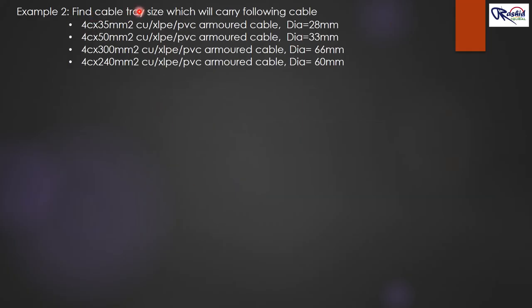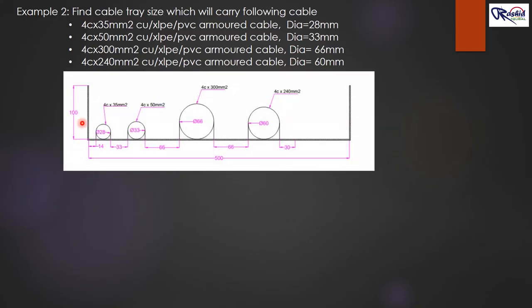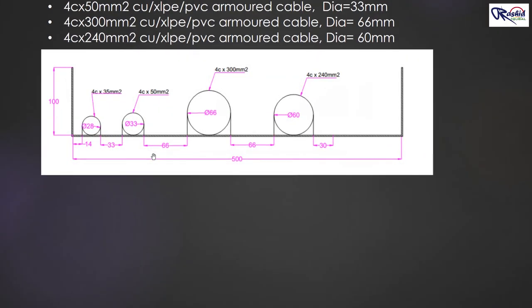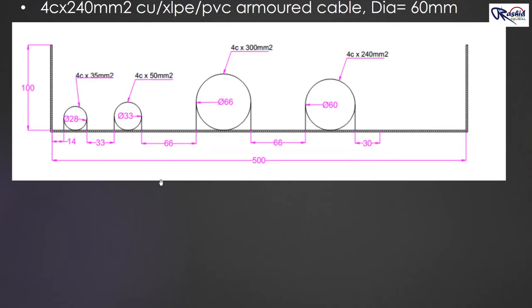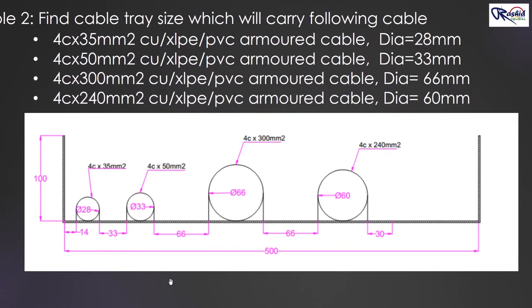Let's see one more example. Find the cable tray size which will carry the following cables: 4-core 35 mm² armored cable with diameter 28 mm; 4-core 50 mm² with diameter 33 mm; 4-core 300 mm² with diameter 66 mm; and 4-core 240 mm² with diameter 60 mm. All cables are armored type. You can see the arrangement following the same rules, with all cable diameters labeled in the layout.